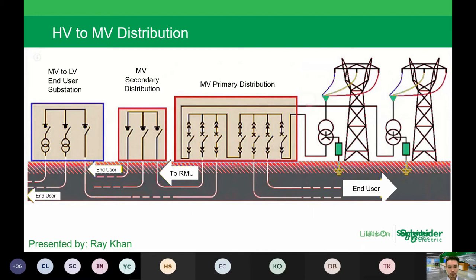Just to share, for primary distribution, most of the time the switchgear deployed is the air insulated switchgear and the gas insulated switchgear. The reason they are chosen is because of the higher fault rating they are able to withstand, and also their protection schemes are much more complex.